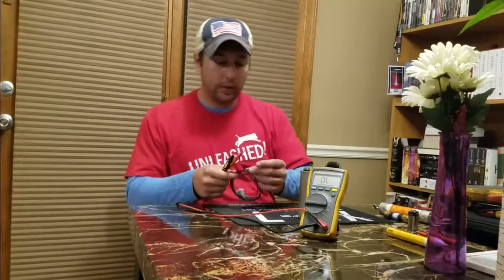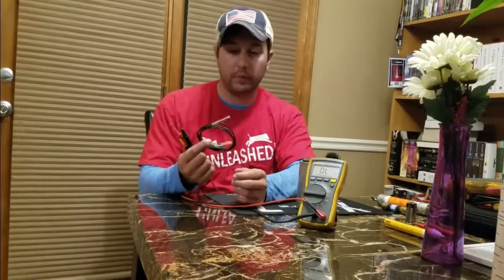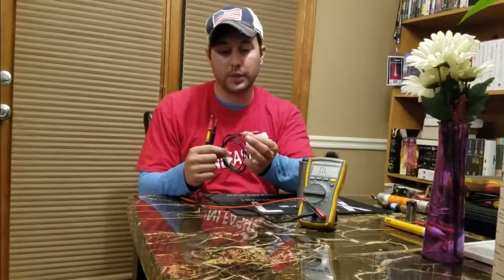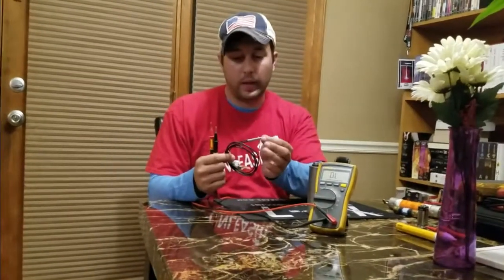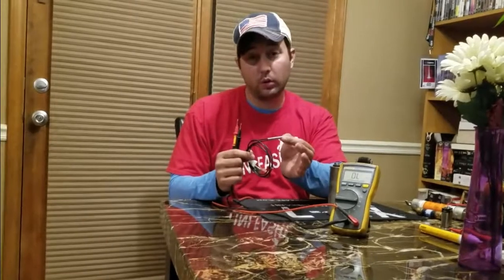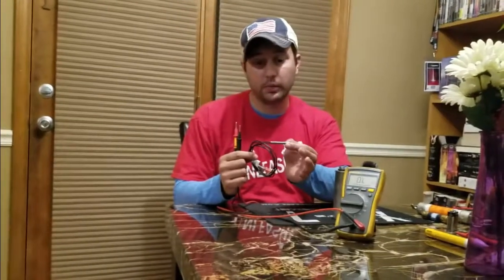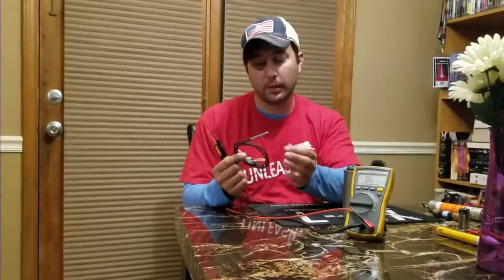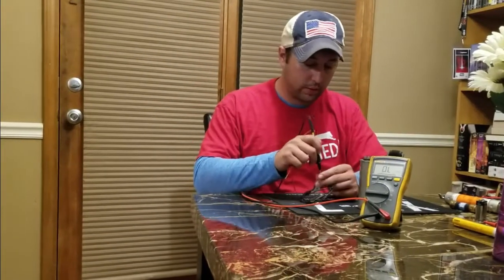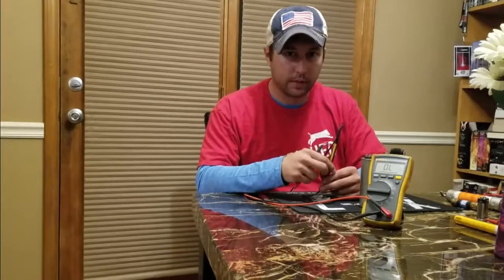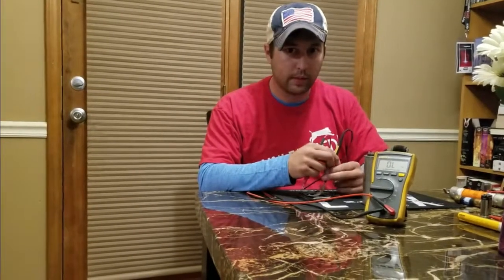You paid for it. This is a temperature sensor I pulled out of a large commercial unit at work. These work off of resistance, and the controller converts the resistance value from the sensor into a temperature value. This one is bad — it shows like 10,000 or something, when it should show like 70.